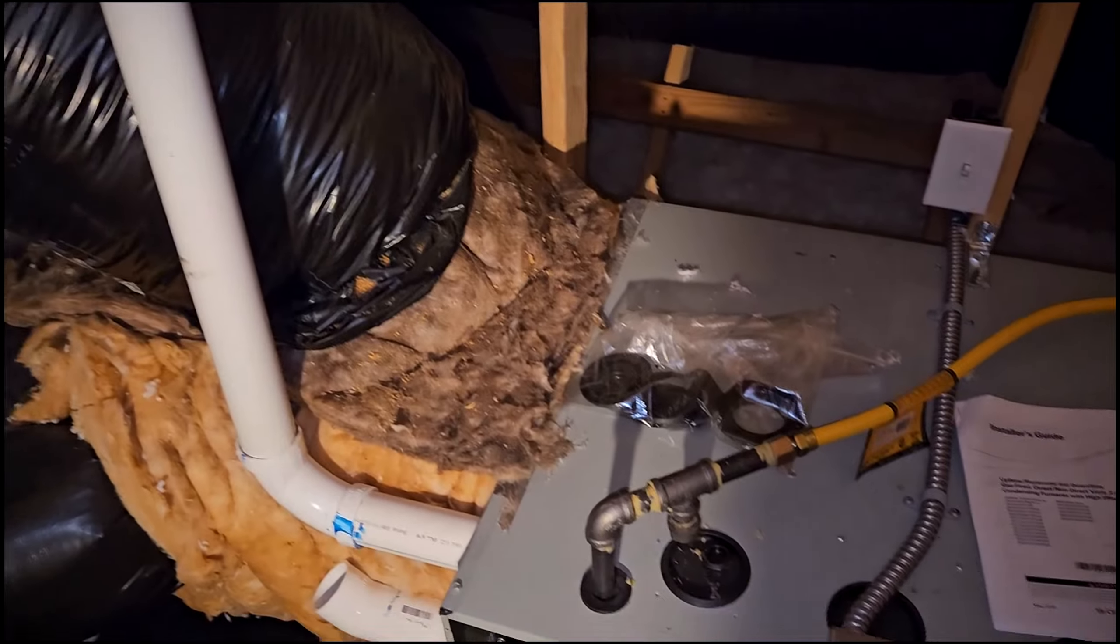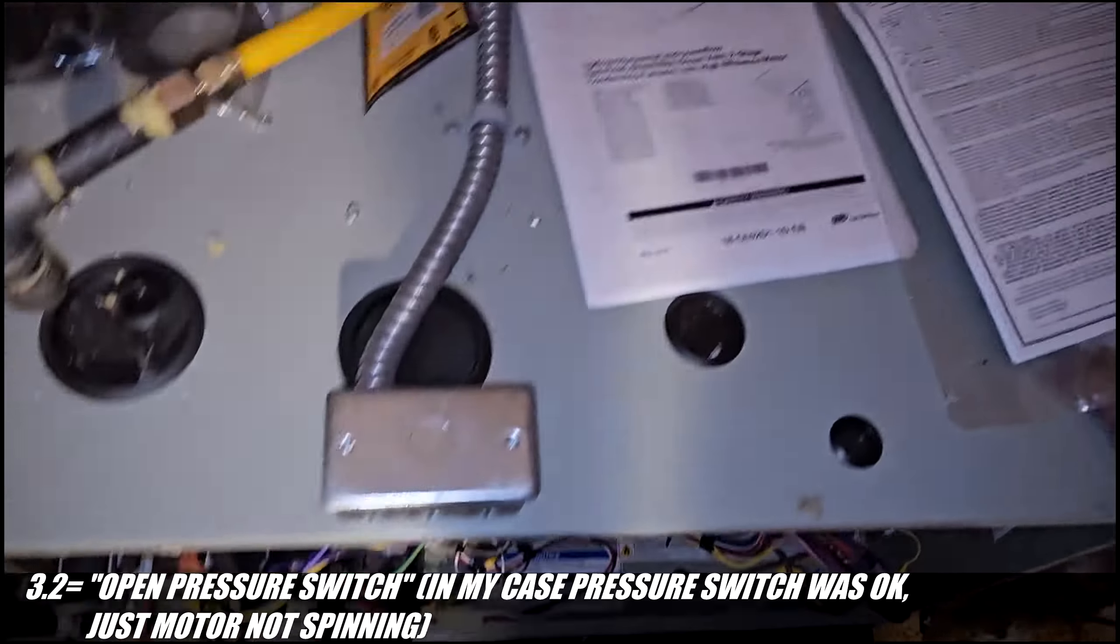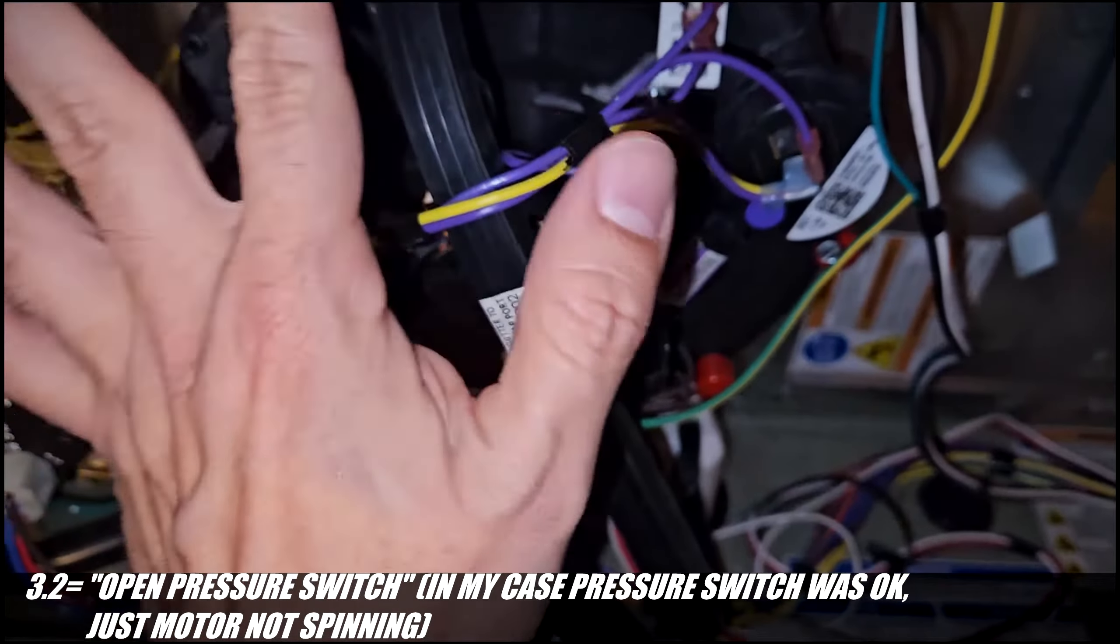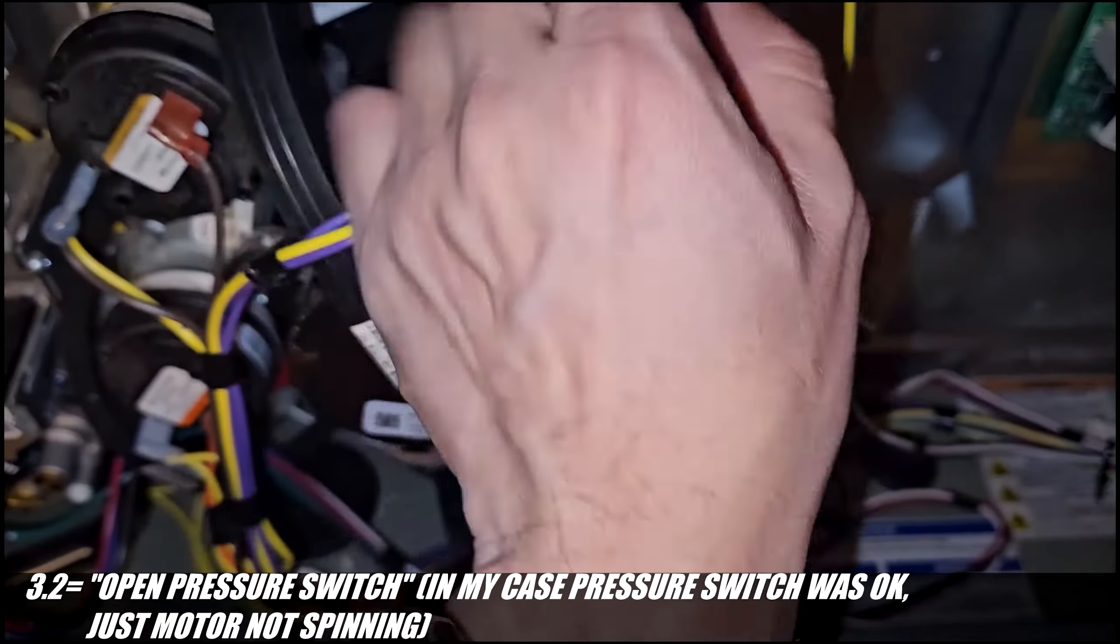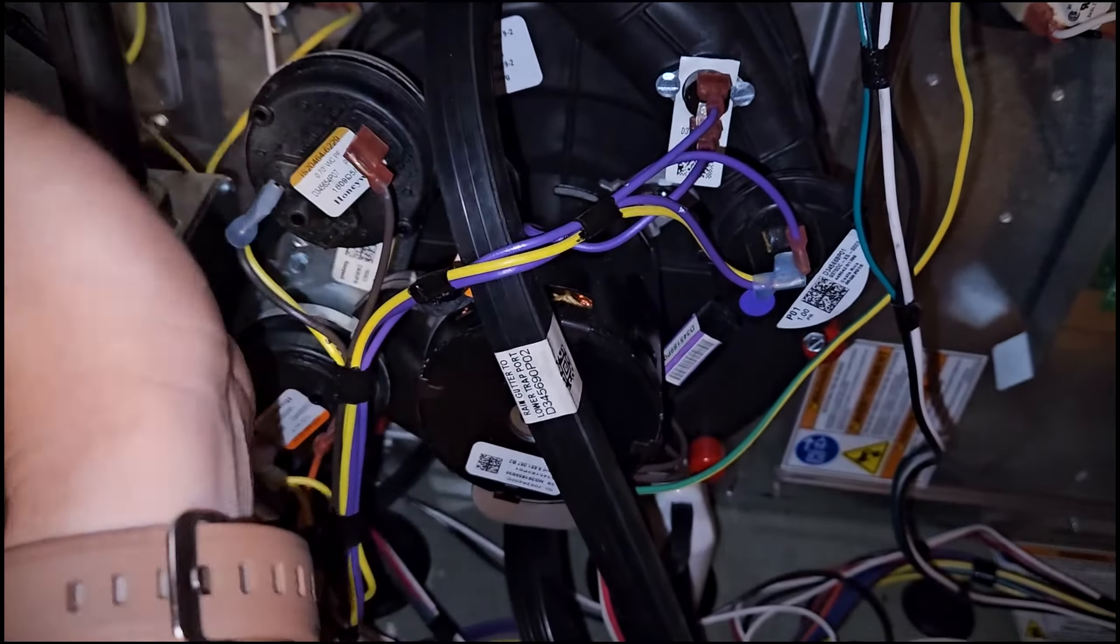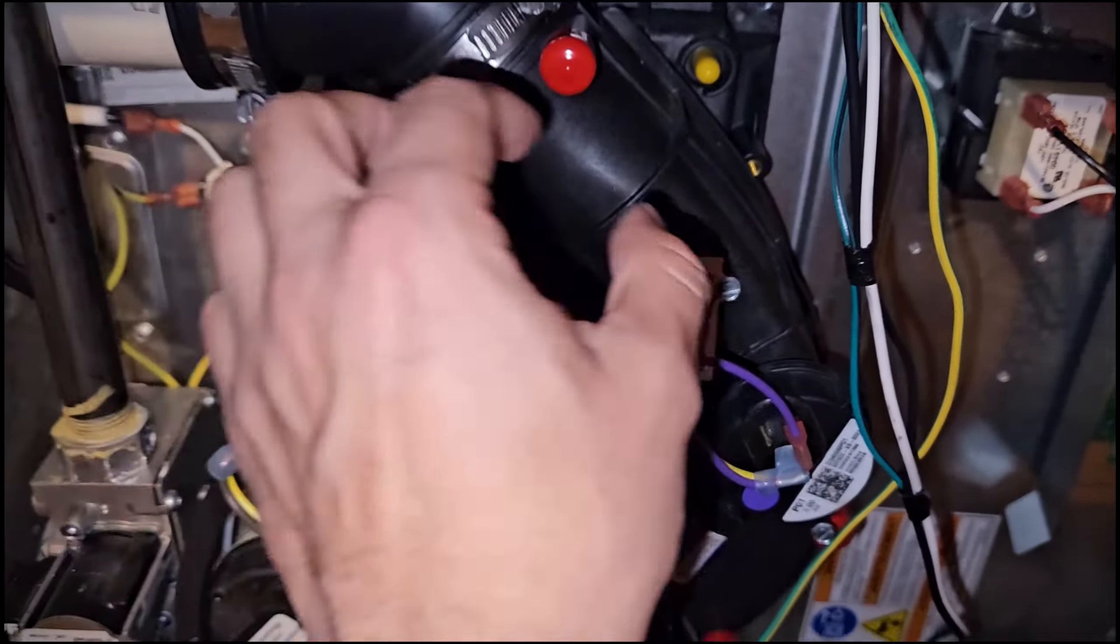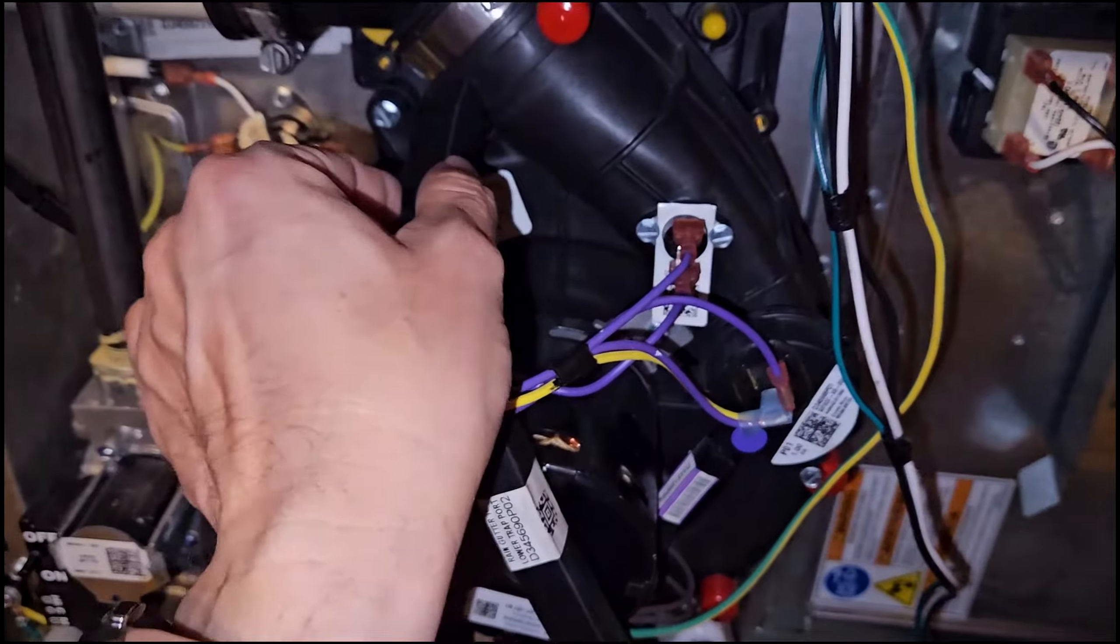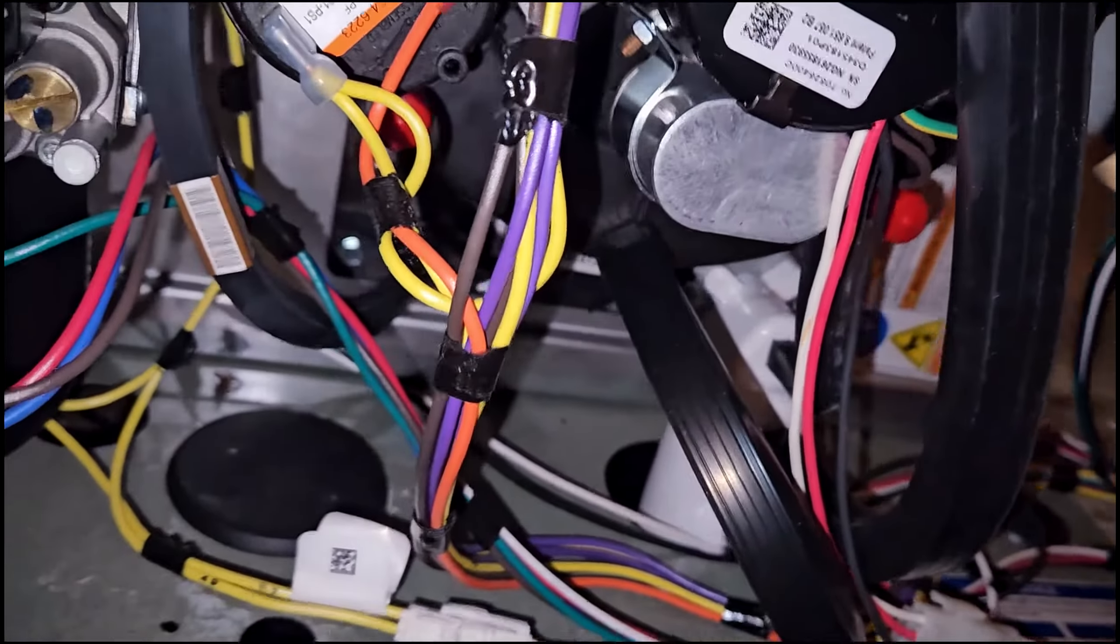Yep, so that's it. Hopefully this video helps somebody. So code 3.2, it was for a pressure switch. In my case, it was that this motor was not spinning and not creating pressure because a pine cone was stuck here. So I had to take this out carefully, take this out, take this out. No, I took this out, split it, I disconnected a few things here. And everything looks okay after one day.